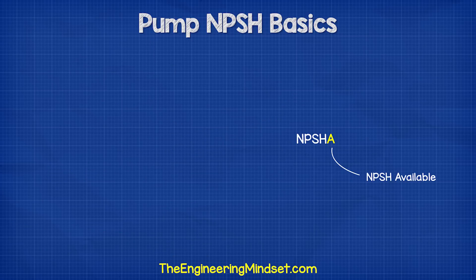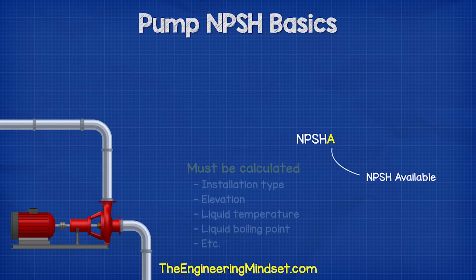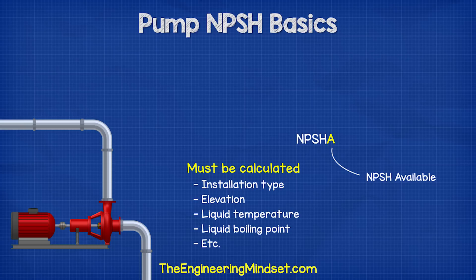The other letter is the A, and this is the NPSH available. This depends on the installation of the pump and needs to be calculated. It considers things such as installation type, elevation, liquid temperature, liquid boiling point, et cetera.